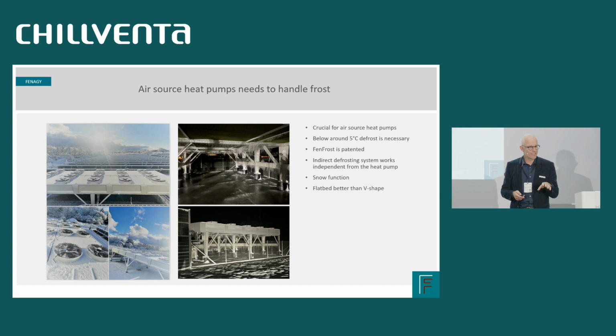We also have what we call the city weather button. City weather is for a heat pump in very humid conditions, just around 1 or 2 degrees. We cool the air down and we get sub-zero temperature, and all the water in the air freezes to ice. And the ice will settle on the fan or the diffuser. We need to avoid that. What we can do here is simply to increase the fan speed. And it's a really effective way to avoid shitty weather problems, I would say.